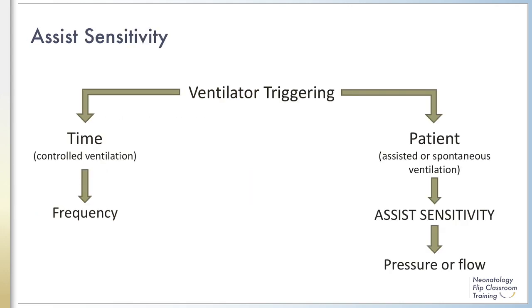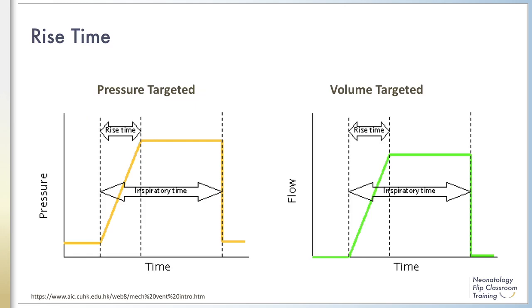The assist sensitivity determines how easy it is for the patient to trigger the ventilator to deliver a breath. The sensitivity setting is the threshold value for the trigger variable which, when met, starts inspiration. Increased sensitivity improves patient-ventilator synchrony, but excessively high sensitivity can result in false or auto-triggering, caused by patient movement or condensation of humidity in the ventilator tubing. Assist sensitivity can be flow or pressure-triggered, although flow-triggering is generally more sensitive for smaller patients. The rise time determines the rate of rise of flow in volume control modes or pressure in pressure control modes; very short rise times can be uncomfortable, while long rise times may reduce tidal volume or require higher pressure.